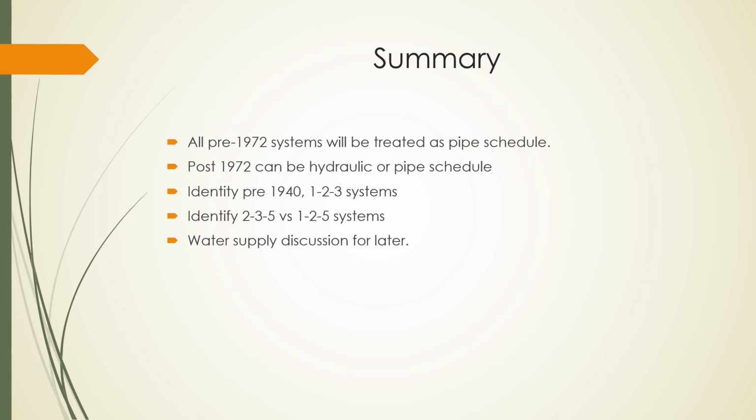I've seen sprinkler systems with 30 psi static, 20 psi residual, and I've seen systems with 150 static and 140 residual. Well, as you can imagine, the 150 psi systems going through the same piping are going to provide significantly more output than a system with 30 psi. I'll show you in the upcoming presentations how to graphically show those differences.